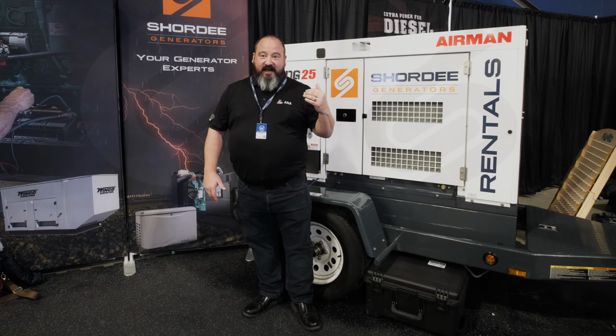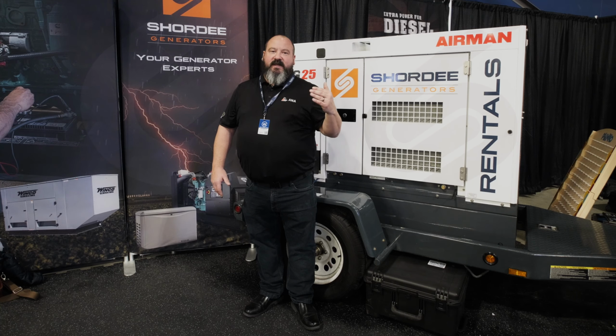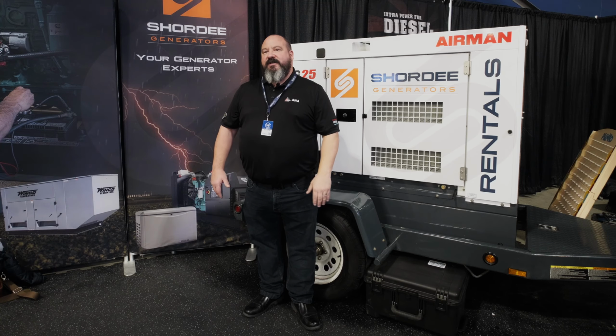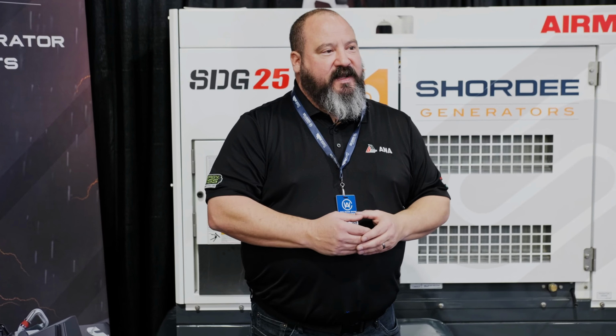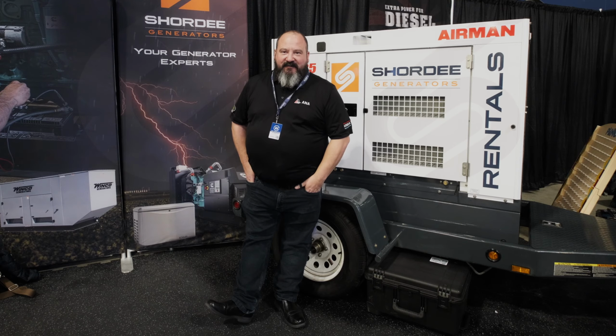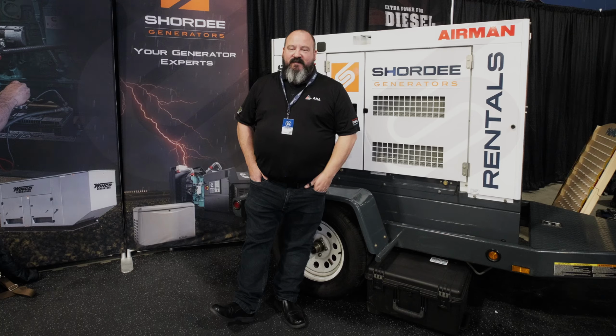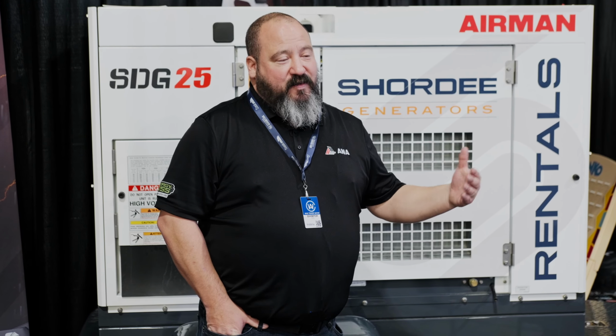As well, we are able to program them. If you're talking about a residential area, sound is very important. We have a very quiet generator to begin with, but we can actually cycle the charge time to bring that battery up to a full state of charge before you go into quiet time, and generally run off of the battery for that whole evening or on one charge during the night, dependent on load. 80% fuel reduction, 70 to 80% emissions reduction, and with the generator running so much less, your maintenance also goes down.